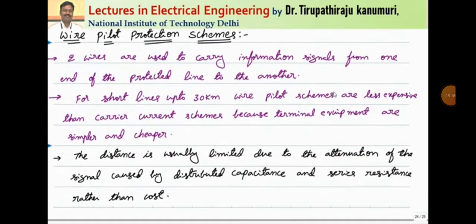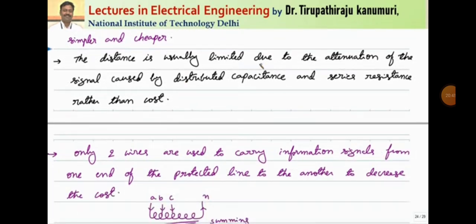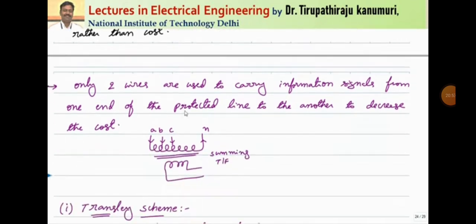Let us start with the pilot wire protection schemes. Because we are employing three-phase protection, for single phase two wires are required, and for three phase at least four wires are required — three for the phases and one for the neutral. To keep costs down, instead of four wires, we use two wires to carry the information signals from one end of the protected line to the other. For short lengths up to 30 kilometers, the wire pilot schemes are less expensive than carrier current schemes because the terminal equipment is simpler and cheaper. The distance is limited due to attenuation of the signal caused by distributed capacitance and series resistance, which is why it is limited between 15 to 30 kilometers.